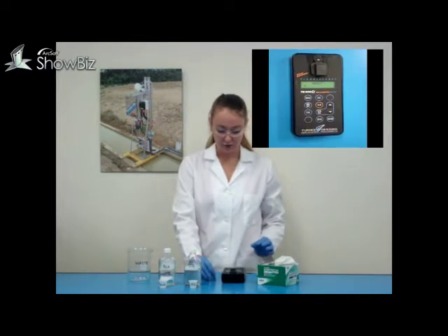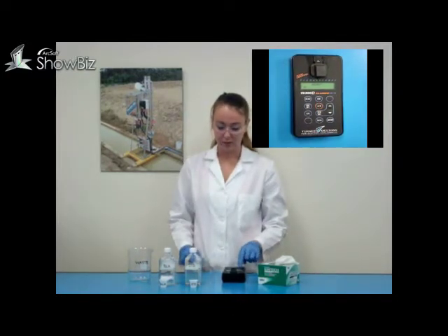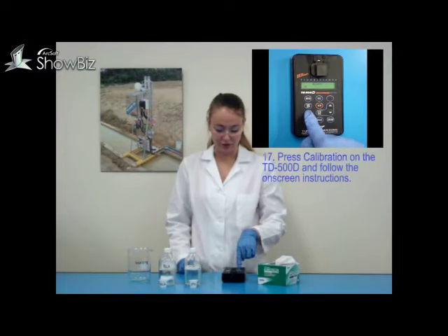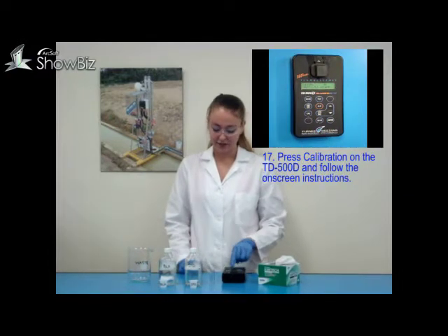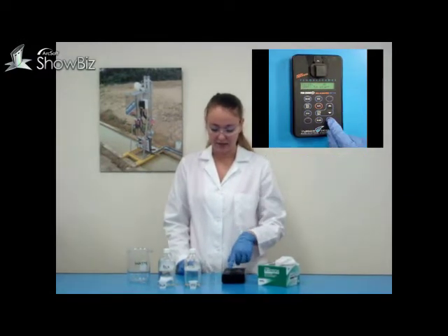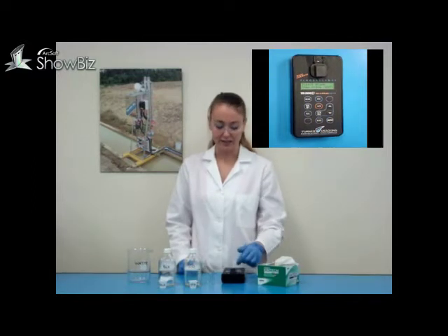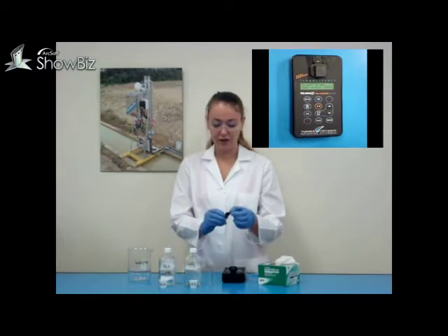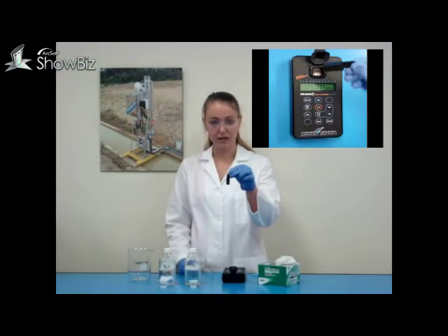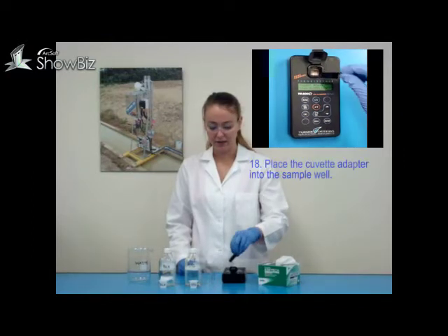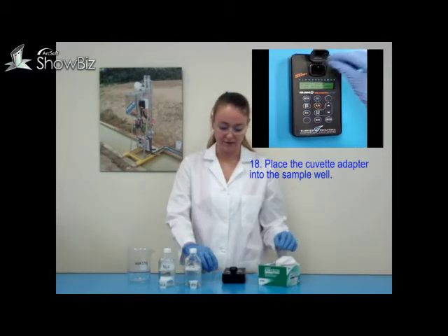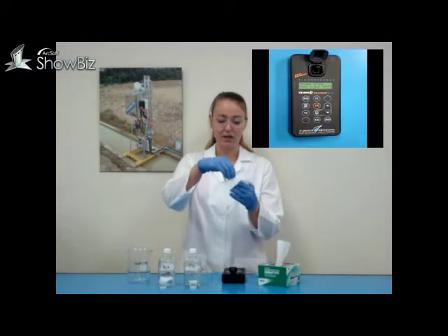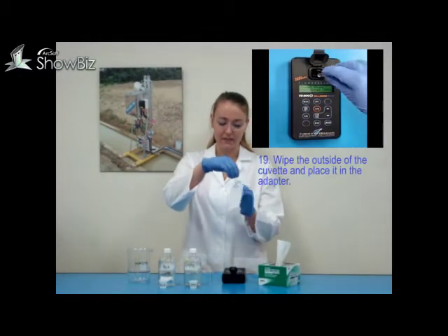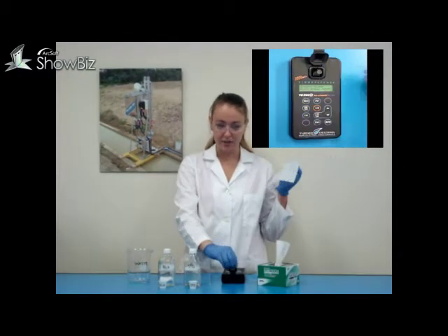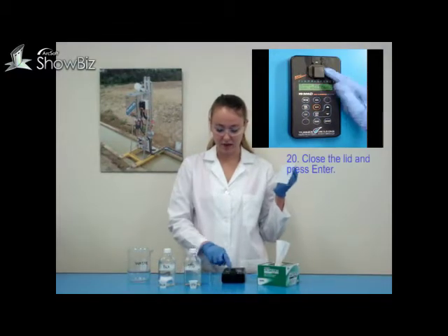To calibrate the instrument, you will push the calibration button and follow the on-screen prompts. It says press enter to start, so you press enter. It says insert blank and then press enter. Make sure you have the appropriate no solvent method cuvette adapter inserted into the TD-500D. Clean the measurement cell with a chem wipe. Place it into the adapter, close the lid, and press enter.